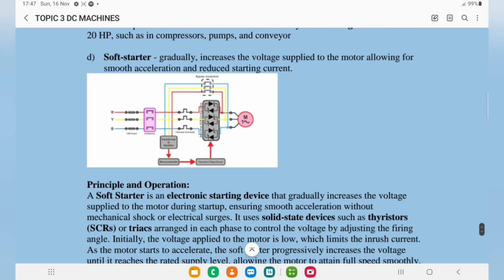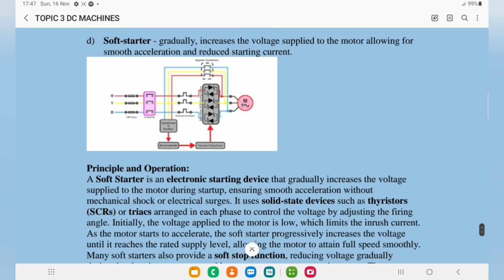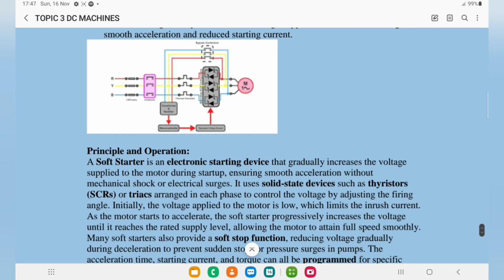We have another method, which is a soft starter, whereby the voltage supplied to the motor is gradually increased, allowing for smooth acceleration and reduced starting current. From the circuit, you can also view the diagram. It is also powered by a three-phase system, which means all the phases are live and transferring current.